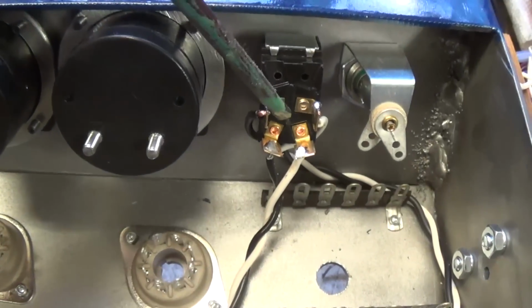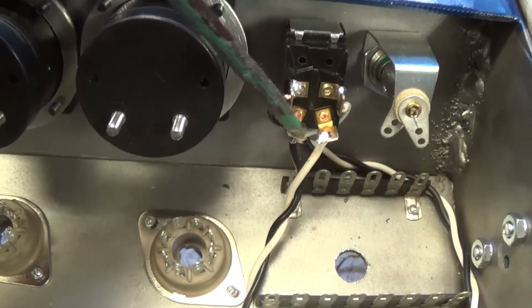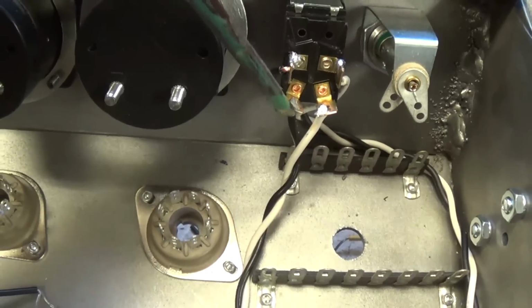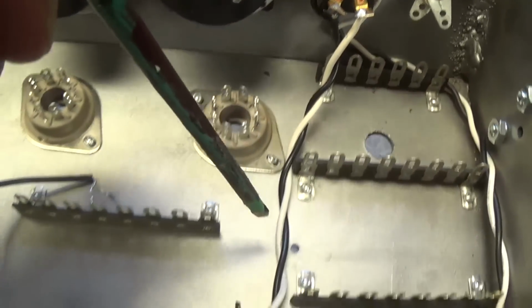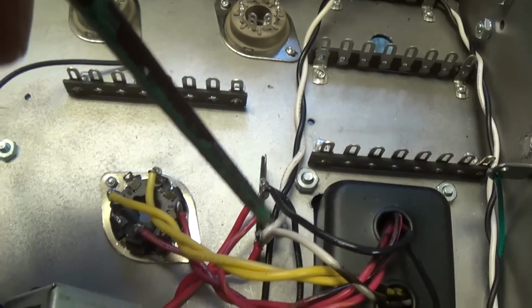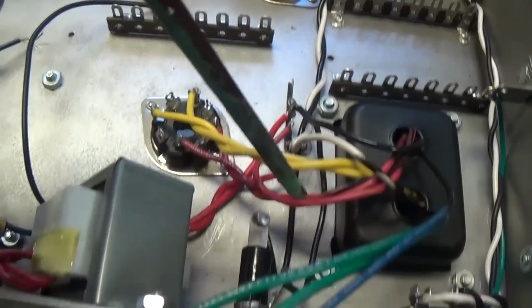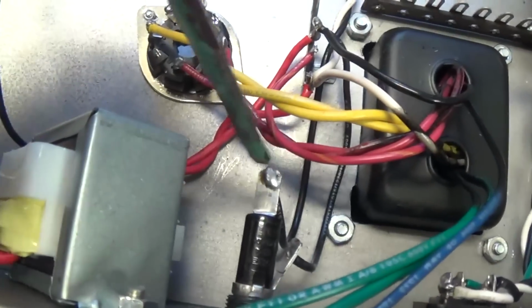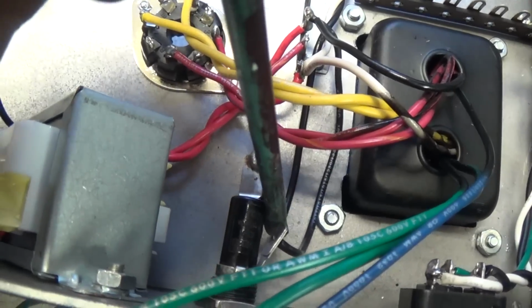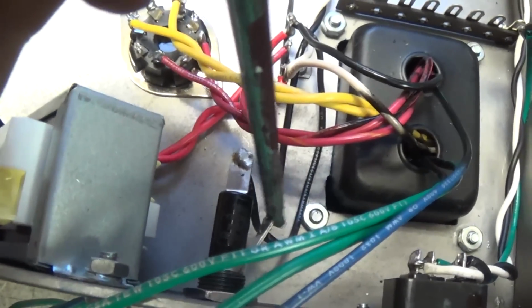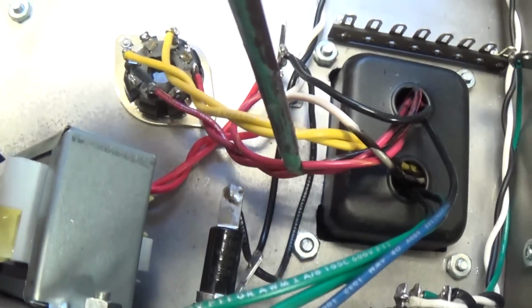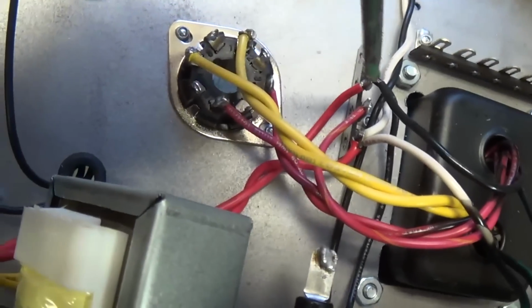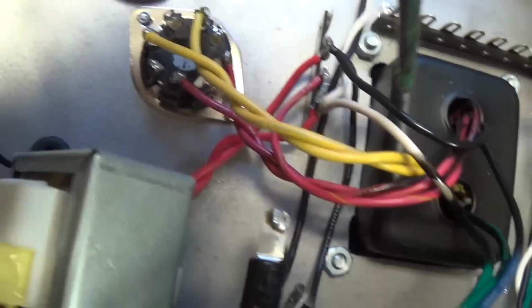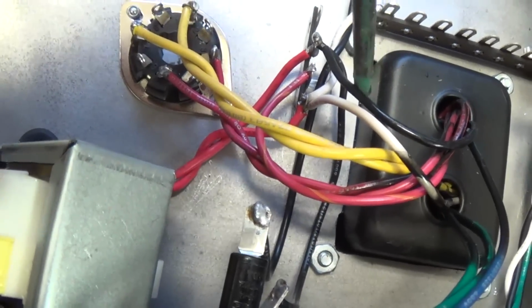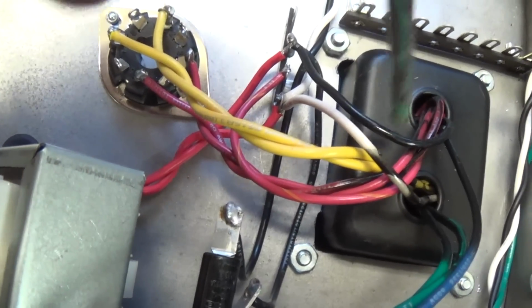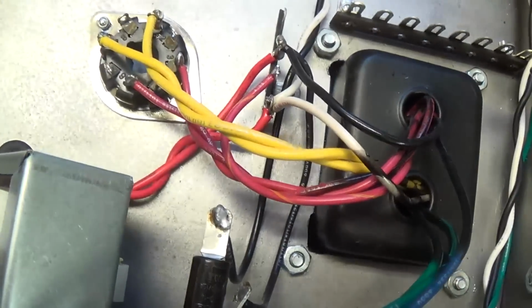The black lead, when the switch is closed, comes down to this terminal and then proceeds, twisted around the return, over to the fuse, to the end of the fuse, and then leaves from the middle terminal on the fuse and comes over to this terminal where it connects to the black wire for the primary of the power transformer.